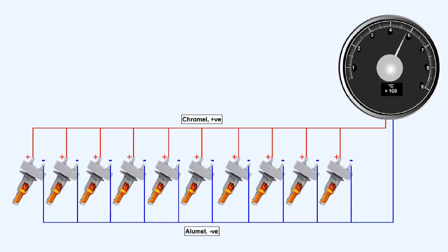To gain complete awareness of the temperature situation, it's necessary to place a number of probes around the periphery of the turbine or the exhaust system. The probes are connected electrically in parallel. Their output is thus the average of all of the probes. Connecting the probes in parallel has the added advantage that if one probe is damaged, their electrical output, and therefore the temperature reading on the gauge, is virtually unaffected.